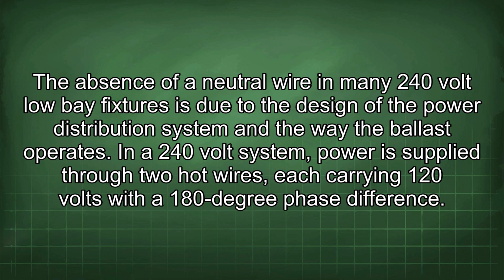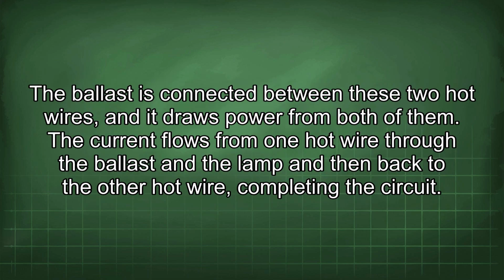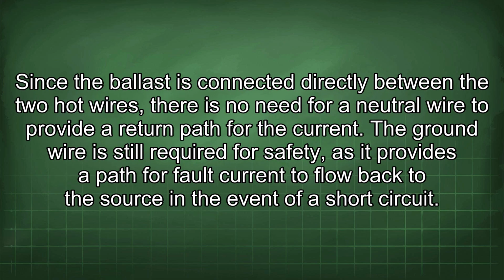The absence of a neutral wire in many 240-volt low-bay fixtures is due to the design of the power distribution system and the way the ballast operates. In a 240-volt system, power is supplied through two hot wires, each carrying 120 volts with a 180-degree phase difference. The ballast is connected between these two hot wires, and it draws power from both of them. The current flows from one hot wire through the ballast and the lamp and then back to the other hot wire, completing the circuit. Since the ballast is connected directly between the two hot wires, there is no need for a neutral wire to provide a return path for the current. The ground wire is still required for safety, as it provides a path for fault current to flow back to the source in the event of a short circuit.